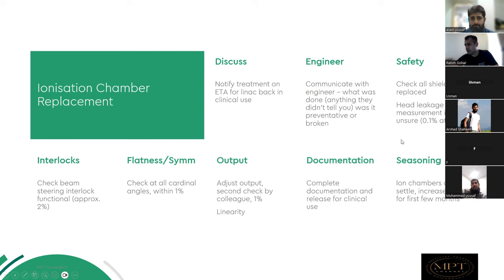New ionization chambers change their behavior over time if they are new. So the output needs to be adjusted on a weekly basis, especially for the new ones. And you have to monitor them for a period of a month. And then once you get a stable reading, you are good to go.